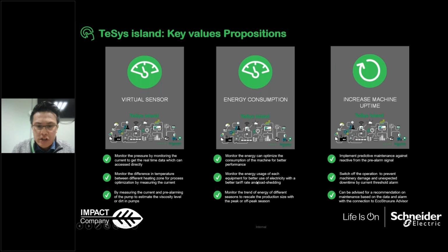Also, by monitoring the energy usage of each piece of equipment, we can make better use of electricity with a better tariff rate and load shedding, especially with this energy crisis that we're facing. For example, if we can see this motor is using more electricity, we can shut off that motor, or shift more load to the other ones, so you can save energy. You can also monitor the trend of energy for different seasons, so you can rescale your production size for the peak or off-peak season. So all of this can be achieved. If we do not have the energy data, you cannot achieve all these values.